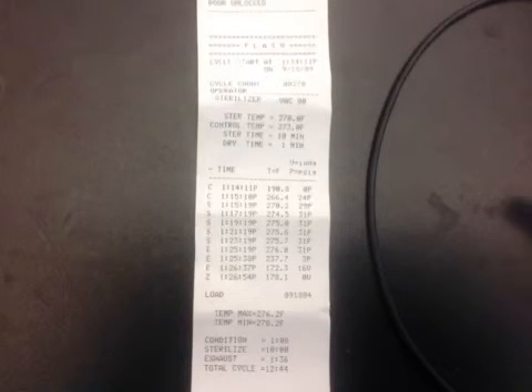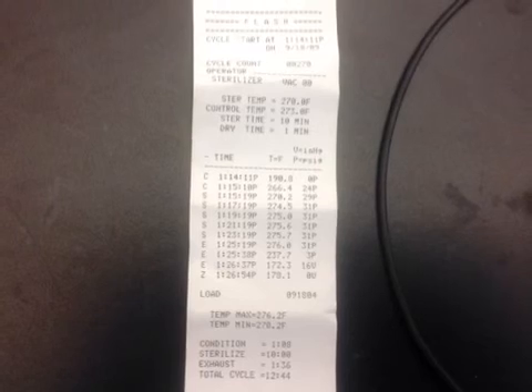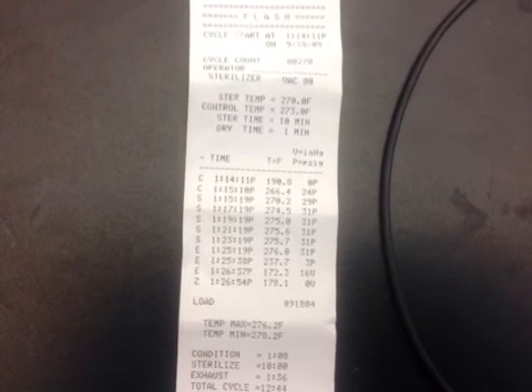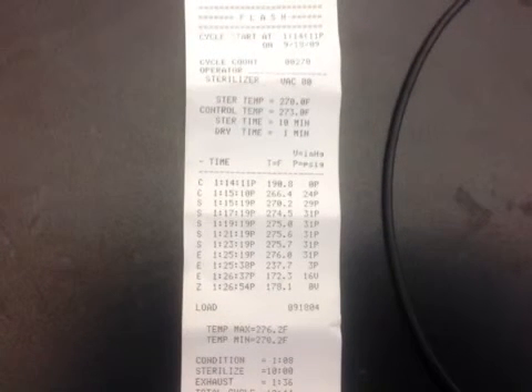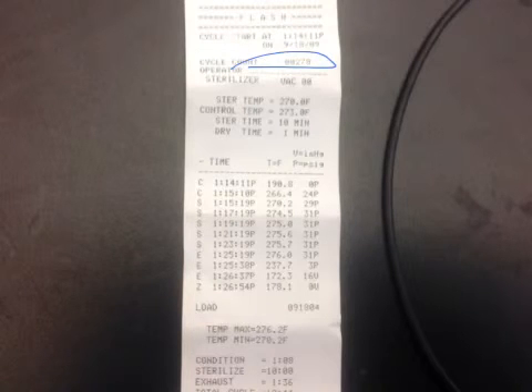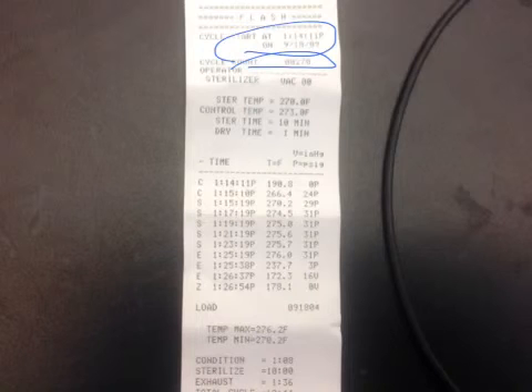Okay, on this second picture, the second readout, this is a 10-minute flash sterilization readout, not flash sterilization, but immediate use sterilization readout. We're going to look here, and our information is also at the top. We got the cycle count, 270. We see the time is 1/14/11 and the date when this cycle began. And we see that it should be set for a 10-minute sterilization, 1-minute dry time.